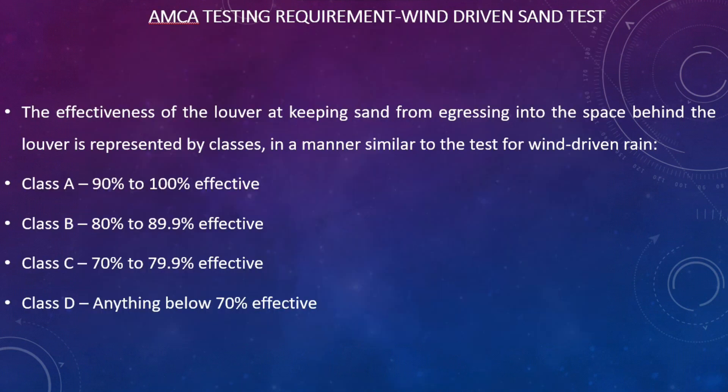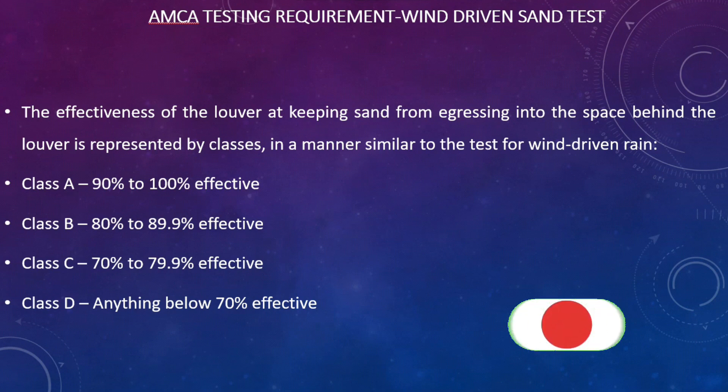After the sand rejection effectiveness, there is one very important thing to consider during selection: the pressure drop. For the same size — for example, a 1000mm by 1000mm sand trap louver — different manufacturers will come with different pressure drops. But it is good engineering practice that the pressure drop of the sand trap louver should not exceed 50 Pascal. We must select a louver with a pressure drop lower than 50 Pascal, and also consider the sand rejection effectiveness.